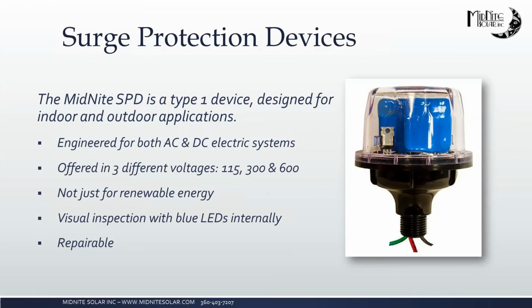Surge protection devices. The MidNite SPD is a Type 1 device designed for indoor or outdoor applications. It is fully sealed so that if you do put it outside in the rain, that won't hurt it at all. It's great for AC and DC electrical systems, and we do offer it in 3 different voltages, 115, 300, and 600. You do want to choose a voltage for your SPD that is above the voltage that you expect to normally see coming into it, because if you are using it with a higher voltage than it is rated for, you will put wear on those MOVs that are in there that are designed to stop the lightning strike from getting to your other electronics.